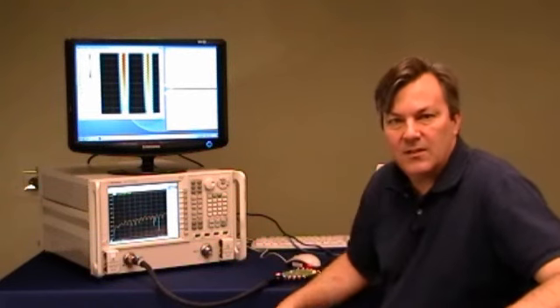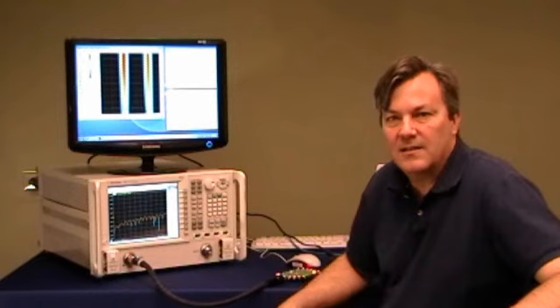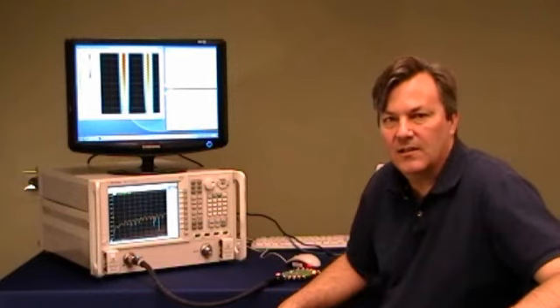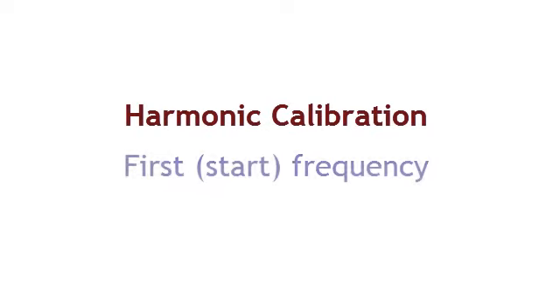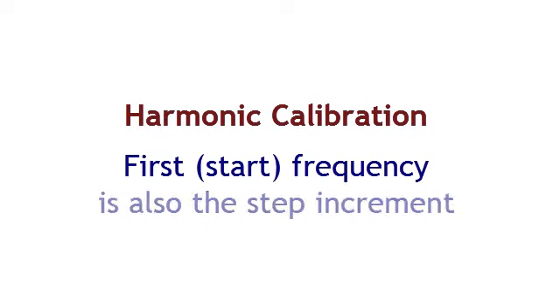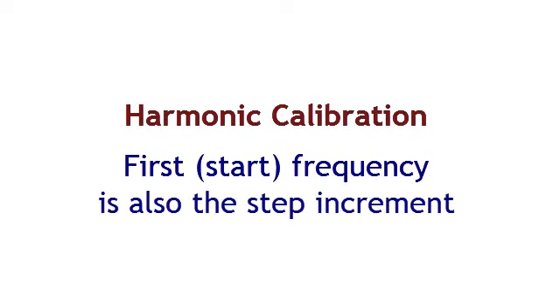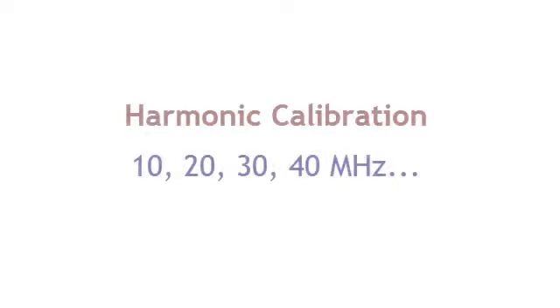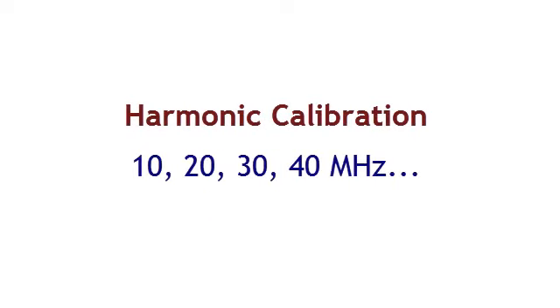Calibration that we like to use in a scenario like this is a harmonic calibration. What harmonic means is the first frequency in your frequency set, which in this case is 10 megahertz, is also the step increment between frequencies. So we want to make a calibration that is at 10 megahertz, 20 megahertz, 30 megahertz, 40 megahertz, and so forth. Everything is a multiple of 10 megahertz.